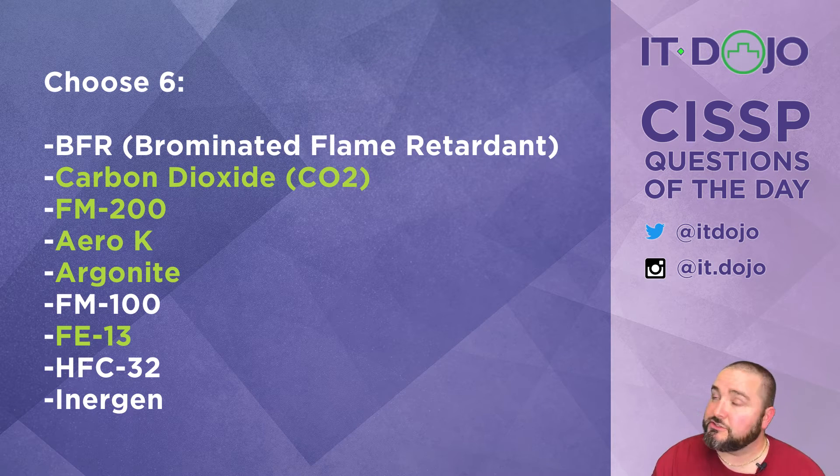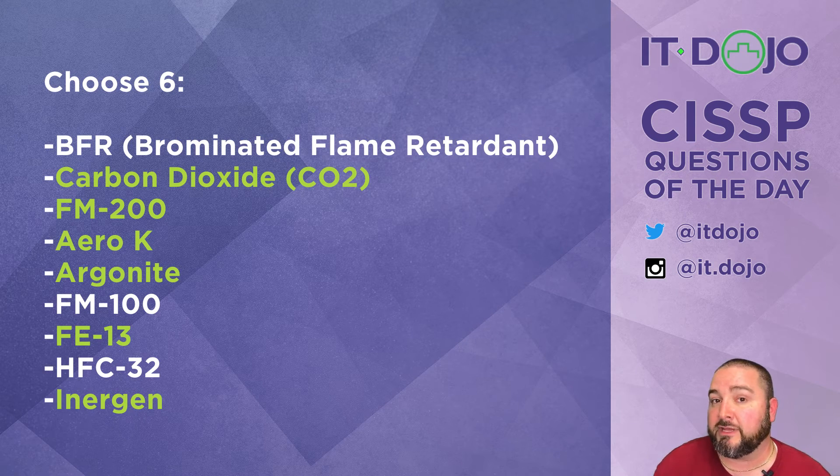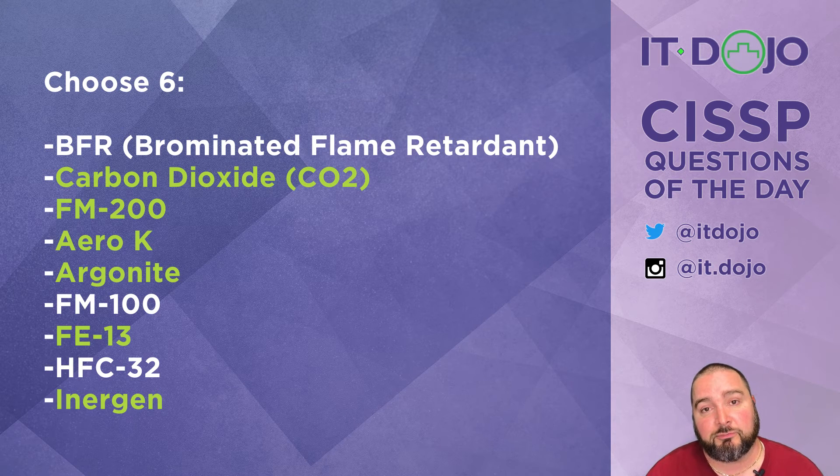Next is HFC 32. HFC 32 is non-ozone depleting; however, it's actually a refrigerant and it's also flammable. Combined with other chemicals it's one of the key ingredients in R-410A, used in many modern air conditioners — so it is not approved. The very last one on the list is Inergen, which is also SNAP approved. Inergen is a combination of carbon dioxide, nitrogen, and usually argon, though sometimes other inert gases including Krypton, making it another SNAP-approved fire suppression mechanism.